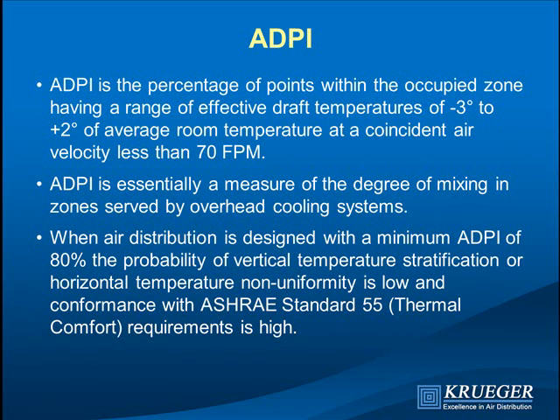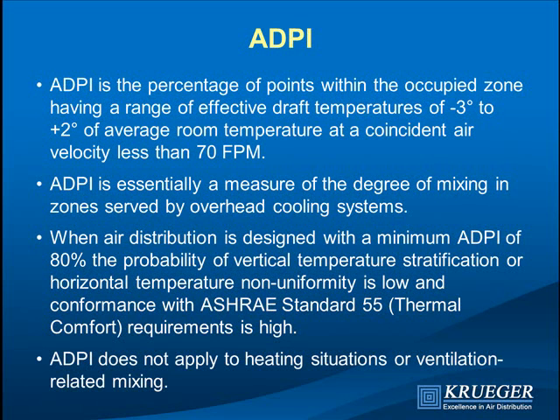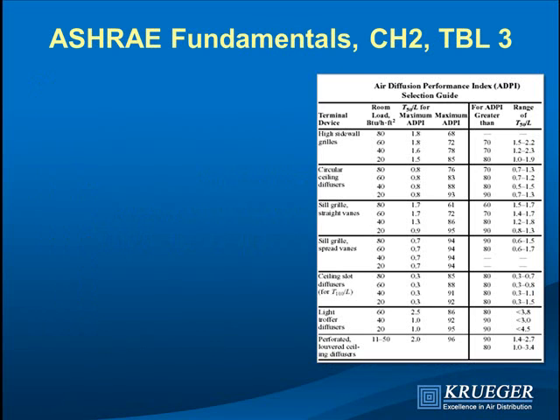When air distribution is designed with a minimum ADPI of 80%, it confirms you likely meet the vertical temperature stratification limits of ASHRAE thermal comfort standard 55, which has a five-degree vertical limit within the comfort zone. ADPI is the only way we know to predict that. Note that ADPI does not apply to heating or to ventilation-related mixing — it is specifically for cold air supplied at the ceiling by a high-induction diffuser.